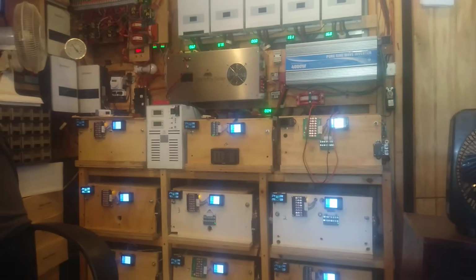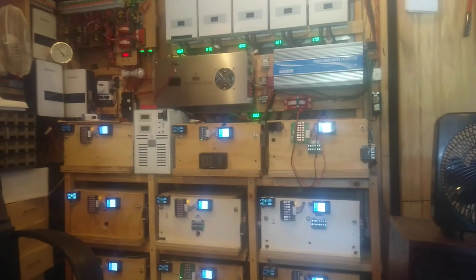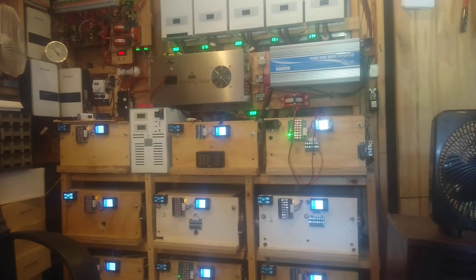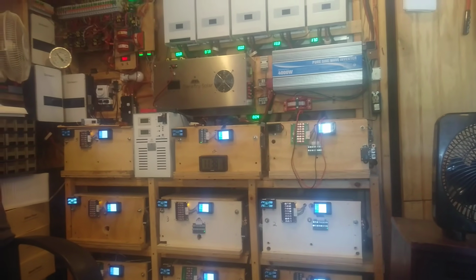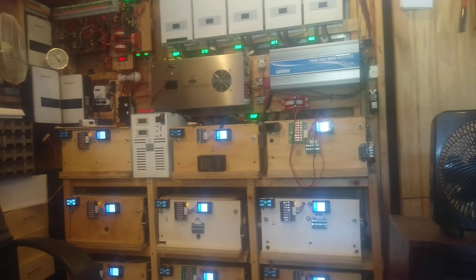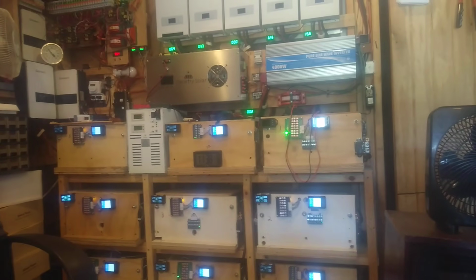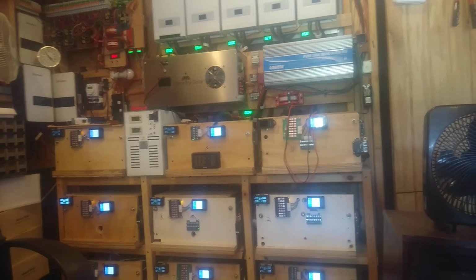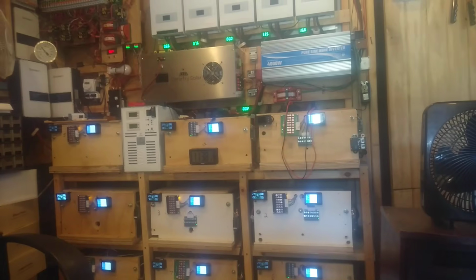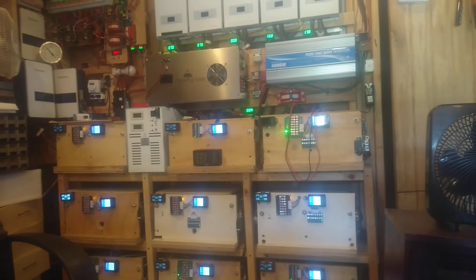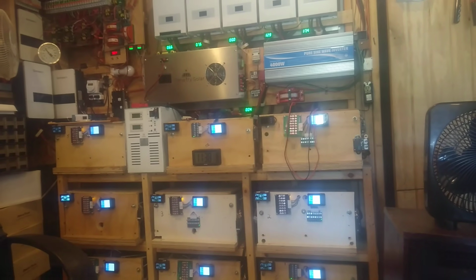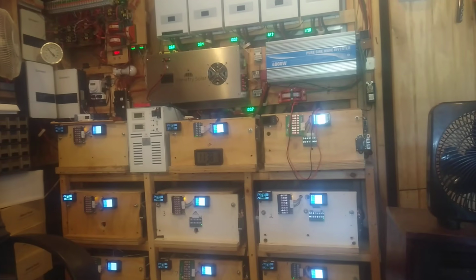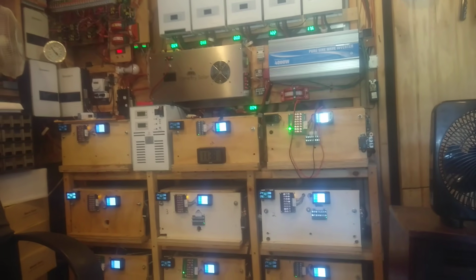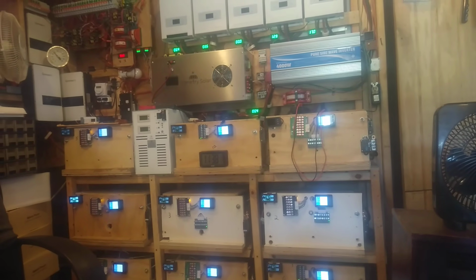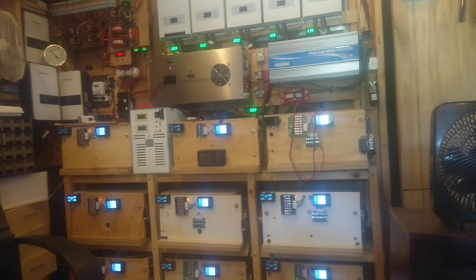For those who don't know, there's knee points on your lithium batteries: a low knee point and a high knee point. That's the cell voltage from the top to the bottom. Down at the bottom knee it's about 3.15 volts - from that point down your batteries will discharge very, very quickly. At the upper end it's about 3.45 volts per cell, and at that point your batteries will charge very quickly.